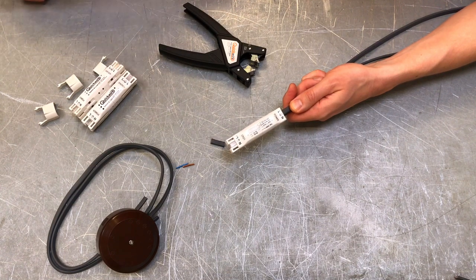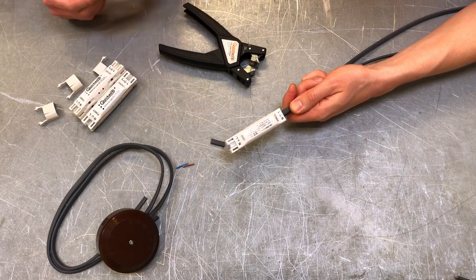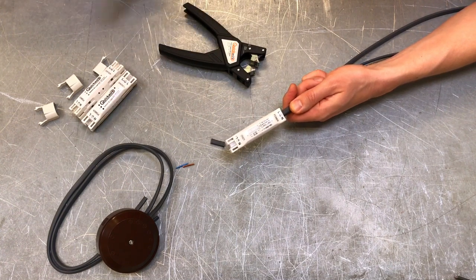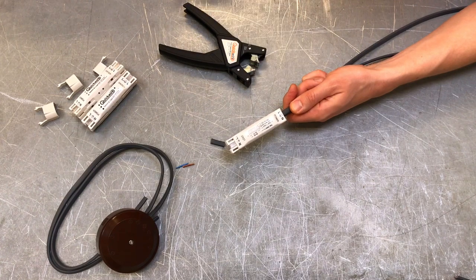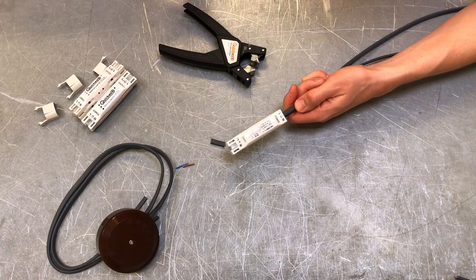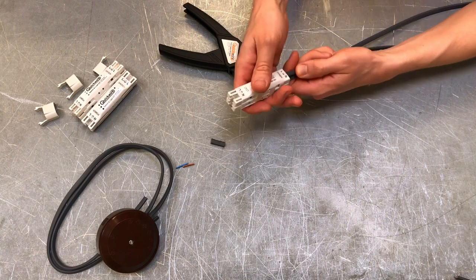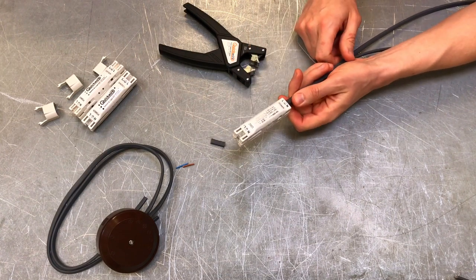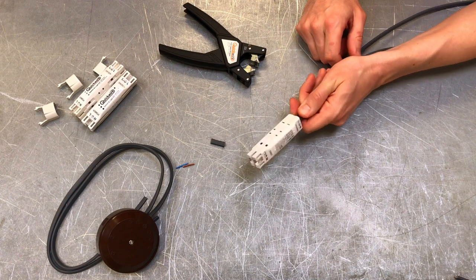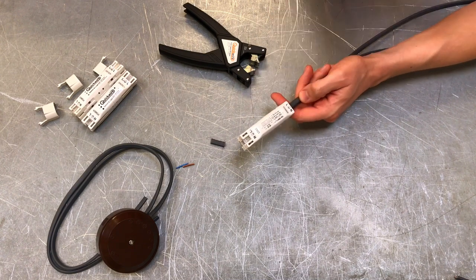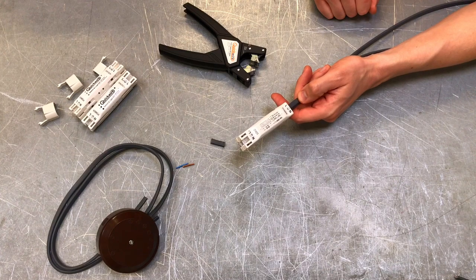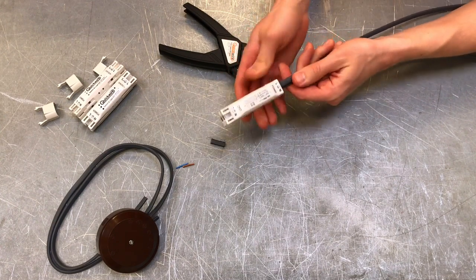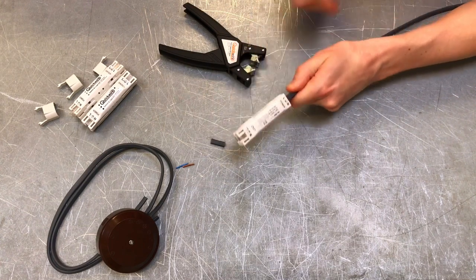It just shows you when we've got a piece of kit that takes away the terminations, screwdriver, the stripping, the dressing, that we've actually made very quick connections and also maintenance-free connections. And cord gripped as well. So it just combines all the very best practice, all the most important things we've got to think about into one box. Because it's maintenance-free, it means we don't need to access those connections to check for tightness in the future, so that could be put somewhere quite safely—no exposed parts, no chance of those cables coming loose.